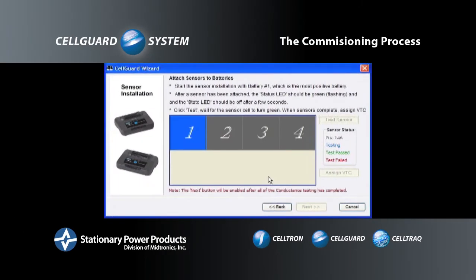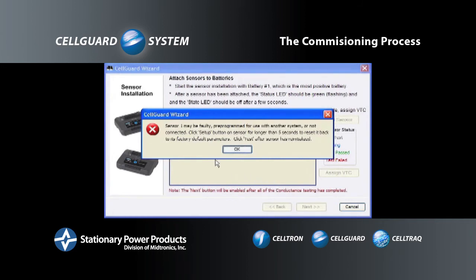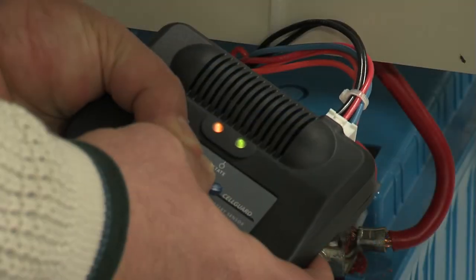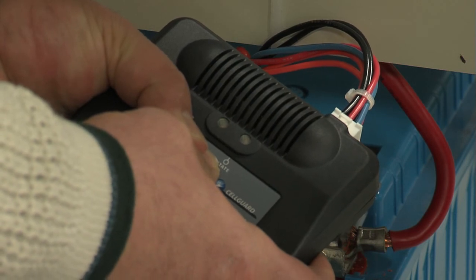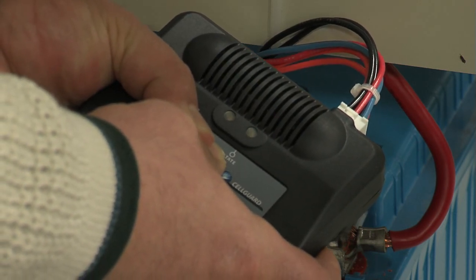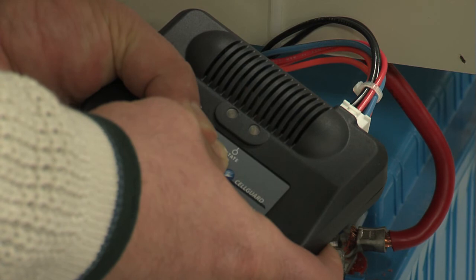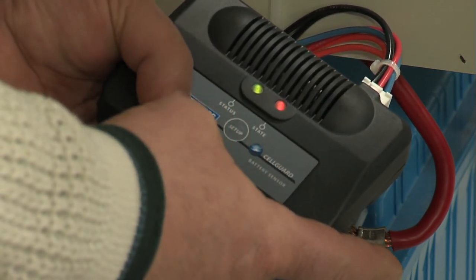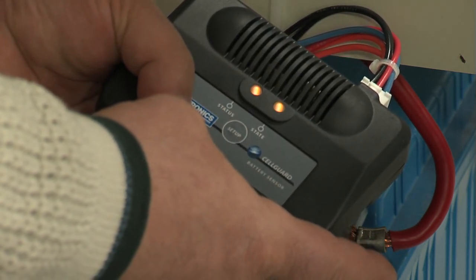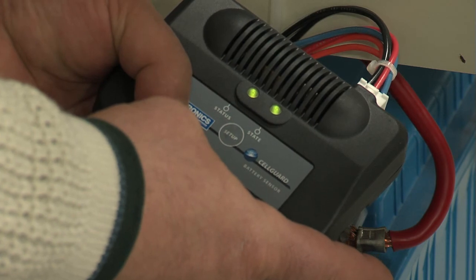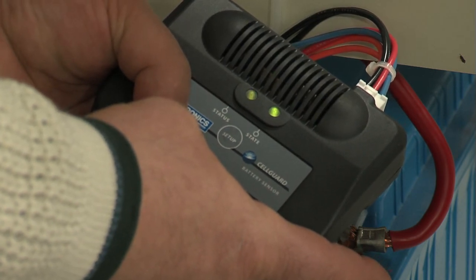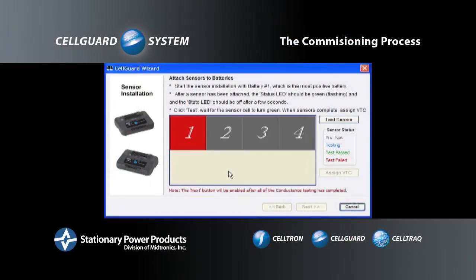If you get a pop-up error message, follow the instructions in the pop-up window and retry commissioning the sensor. Be sure to leave the sensor connected to the battery. Hold down the Setup button on the sensor for more than 5 seconds with the LEDs off. Release the button and wait for the LEDs to go through their power-up sequence. When you see the status LED flashing green, click OK, and then click Test Sensor.